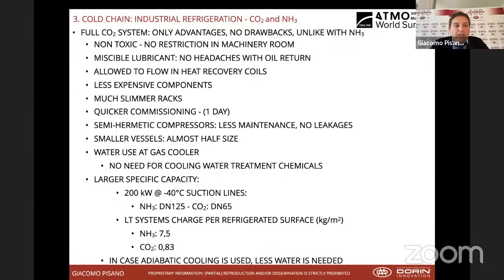Normally, CO2 brings in slimmer racks, so definitely the footprint of the rack is smaller, and this brings cost saving when it comes to building expenses. Commissioning of CO2 equipment is normally quicker. You work with semi-hermetic compressors that feature less maintenance and basically no leakages. When you do a flooded system, vessels are almost half size when talking about CO2.